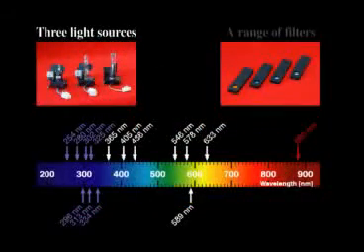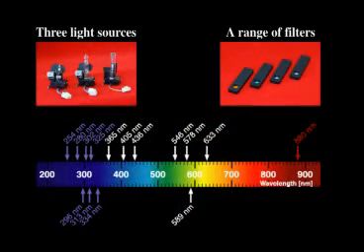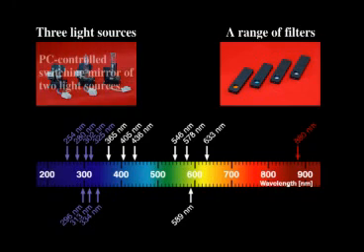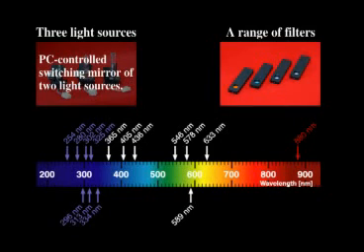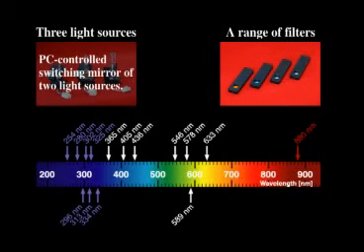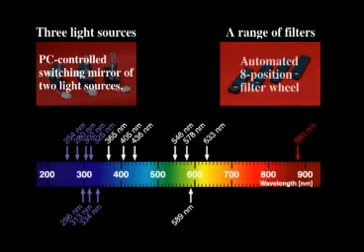Three kinds of light sources and a wide range of filters can be chosen for any individual application. Two light sources can be installed simultaneously in the instrument and selected by a PC-controlled switching mirror. In addition to a manual filter exchange, an automated eight-position filter wheel is available.